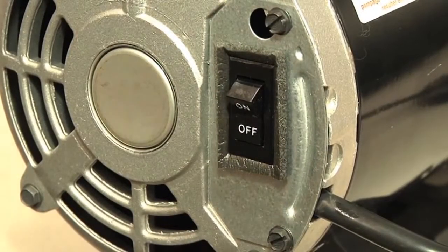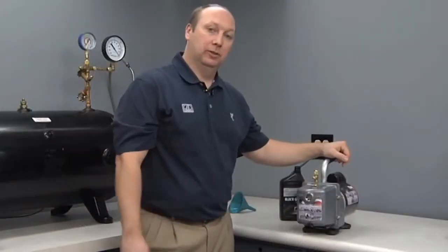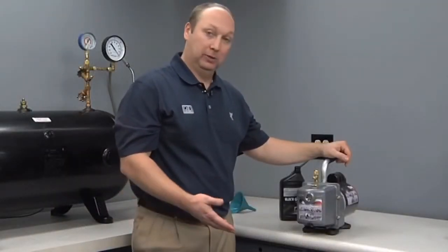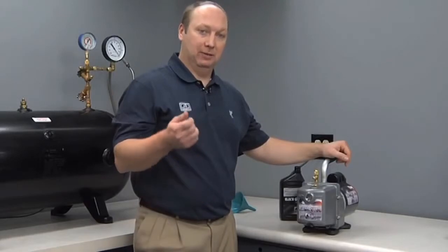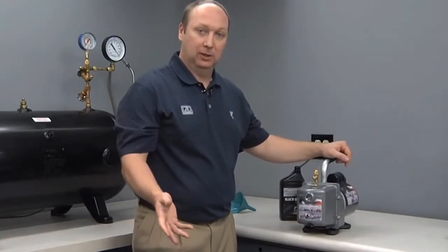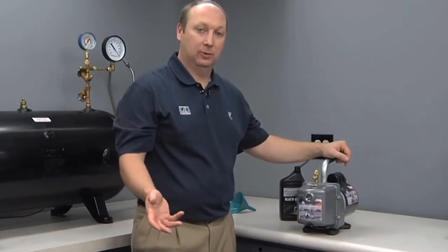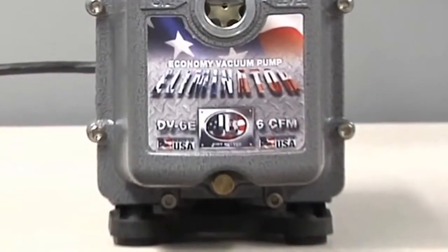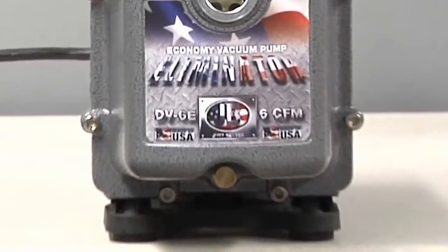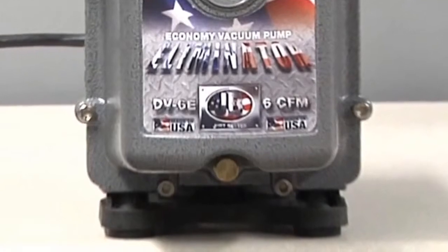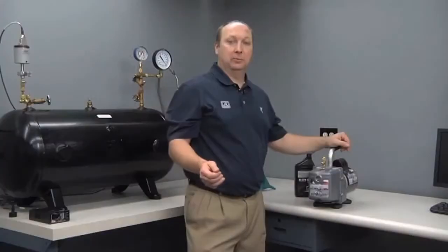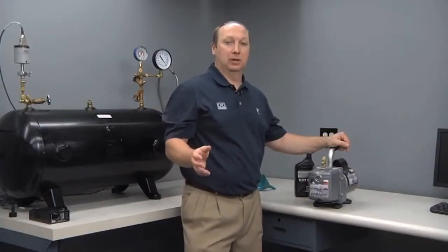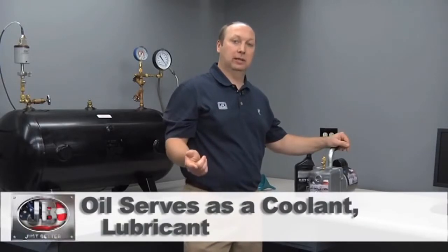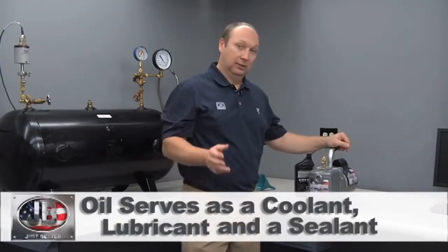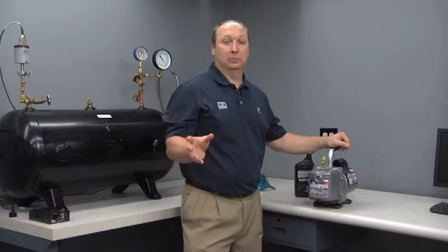Another important feature of the JB eliminator vacuum pump is the oil drain. Many of the competitors just have a screw with an O-ring that falls into an oil pan as you're draining the oil. The JB has a fully functional in-house designed valve which opens and closes against an O-ring seal. The vacuum pump oil serves 3 functions in a vacuum pump. It's a coolant, a lubricant, and a sealant. The oil really is the lifeblood of your vacuum pump, so we recommend changing after every use.